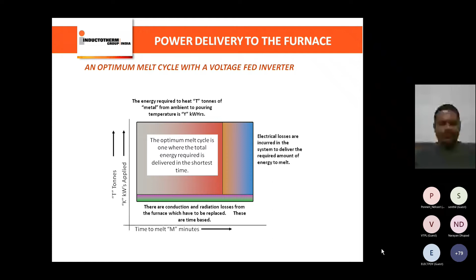An optimum melt cycle with our voltage fed inverter is such that the energy required to heat T tons of metal from ambient to pouring temperature is Y units. Electrical losses are incurred in the system to deliver the required amount of energy to melt, in the form of radiation, conduction, and convection losses. So the optimum melt cycle is one where the total energy required is delivered in the shortest time.